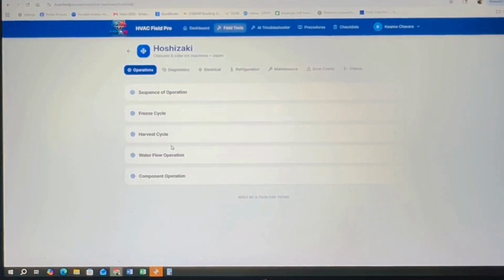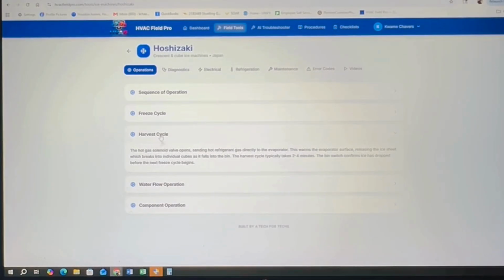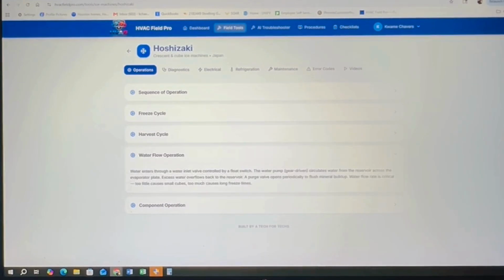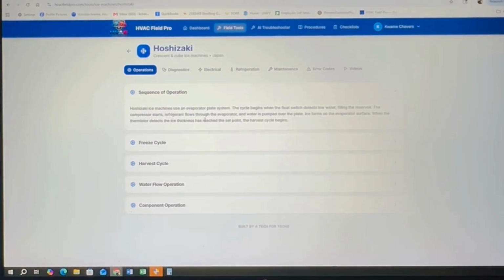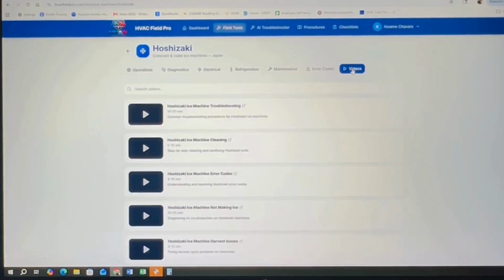And then when you click on that thing, it gives you the sequence of operation, freeze cycle, the harvest cycle, tells you about each one. Hot gas solenoid valves open up, sending hot refrigerant gas directly to, this is the water flow operation, sequence of operation. This is beautiful. Oh, it gets even better, guys.